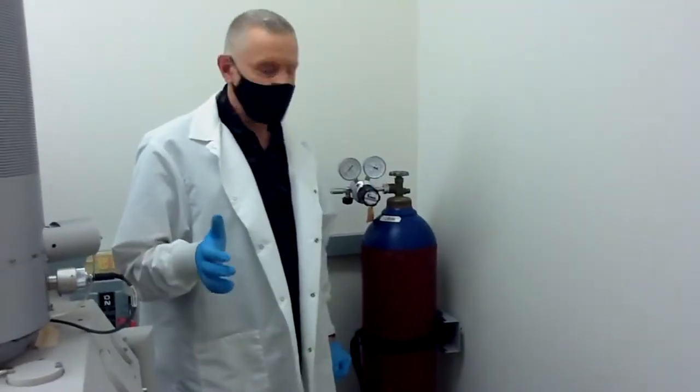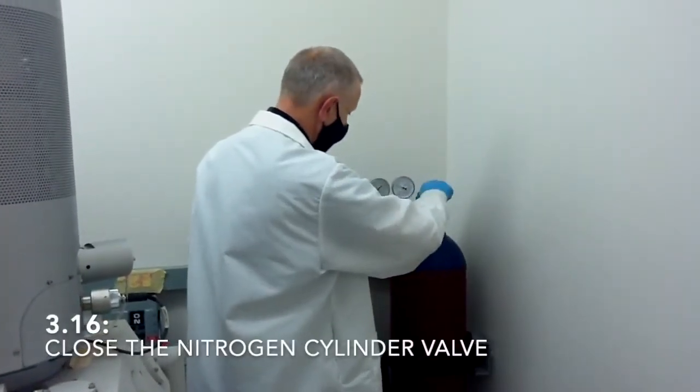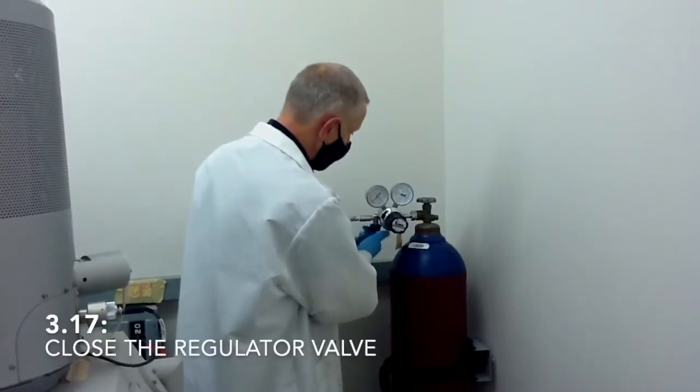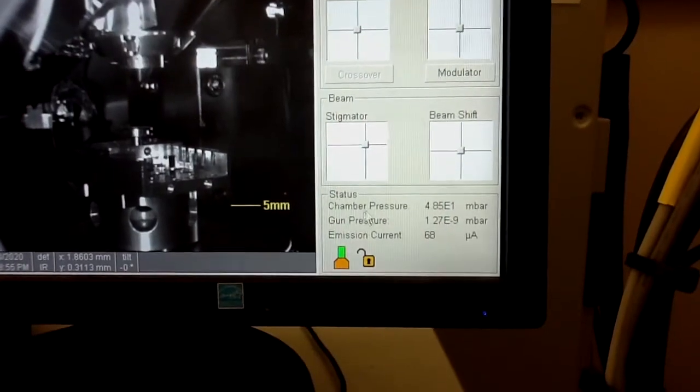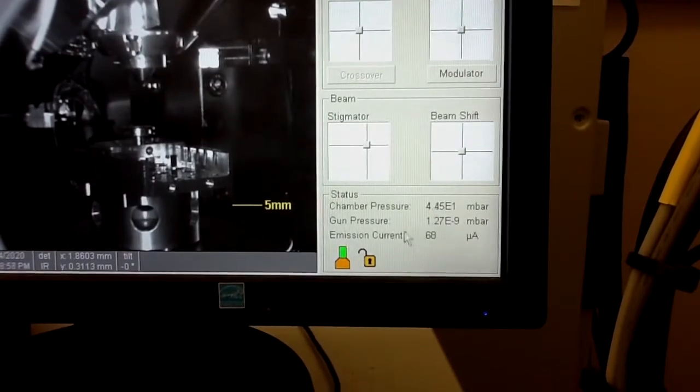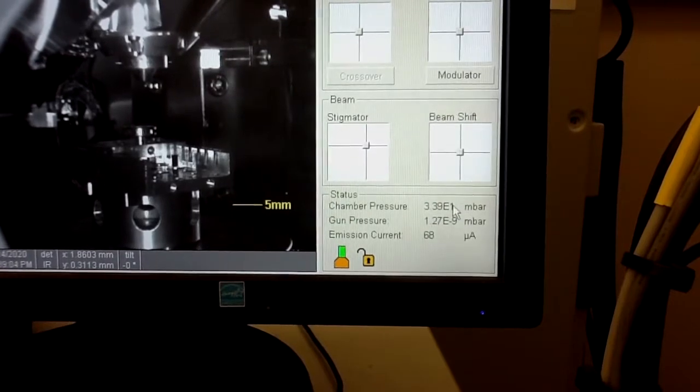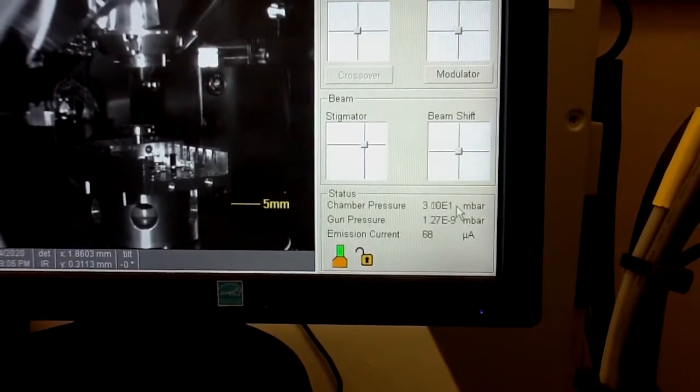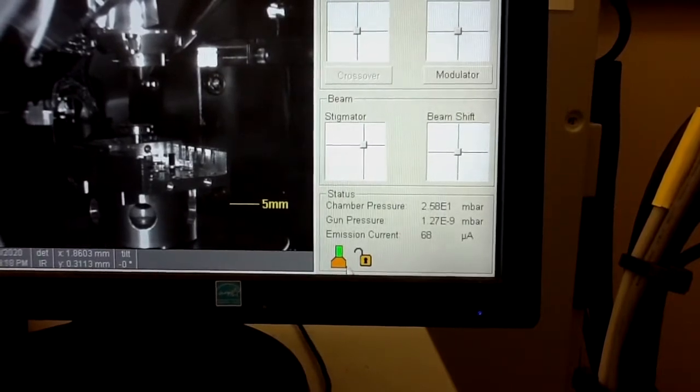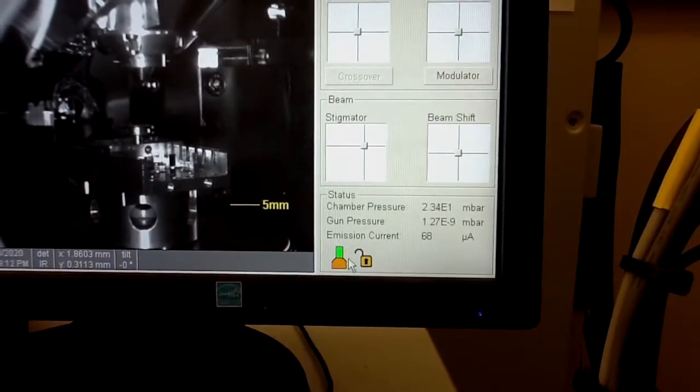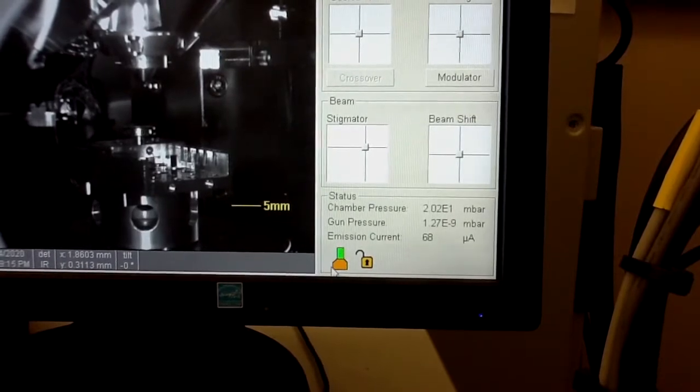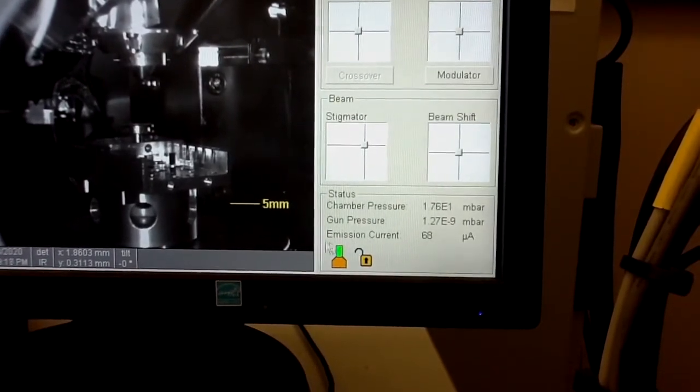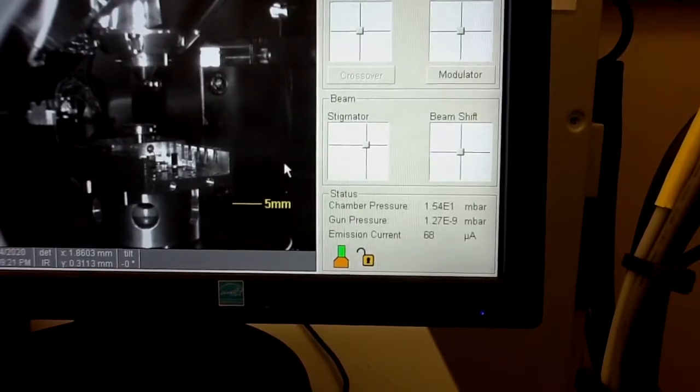After the pumping begins, you have about three minutes. This is a good time to close this valve again, to save nitrogen. And you can also close this one. So now during the pumping, you will notice that this chamber pressure decreases. The vacuum will improve. You have to wait till it's almost in 10 to the minus fifth range. And the best indication is when this icon changes from orange to green, you are able to start high tension and start using the SEM.